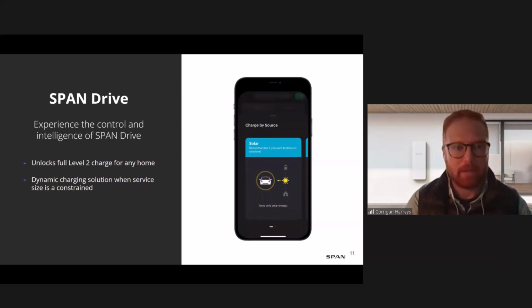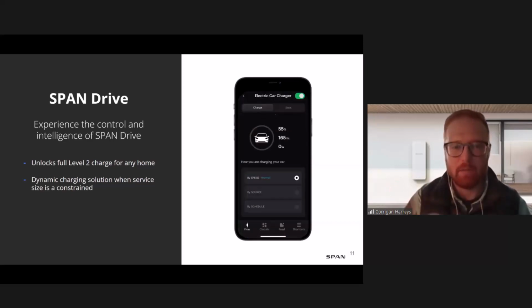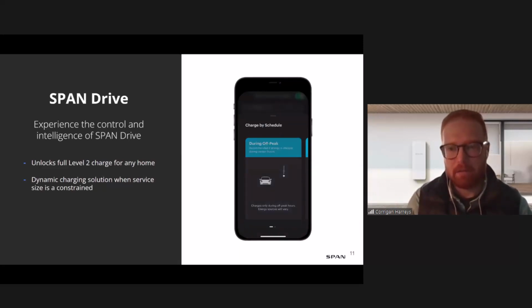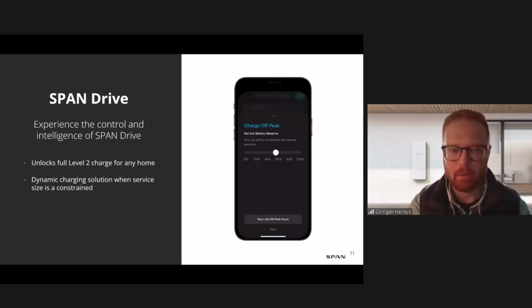So how do we solve this? Because we're an energy management system, the 60 amp breaker doesn't need to be counted during load calculations. Per the NEC code, you don't have to count 60 amps in your total load calcs for the 80% rule.